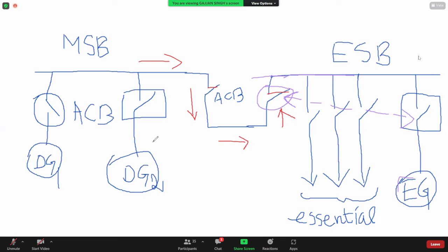Thereafter, the neutral wire is neutral grounded. On shore, it is grounded because of safety. Wherever there is an earth fault, like in your cabin, your cabin breaker will trip. Your friend's cabin, there is an earth fault, your friend's cabin breaker will trip. Wherever there is a fault on shore, there is tripping. Why? Because neutral is grounded.